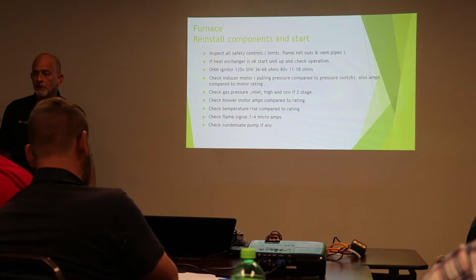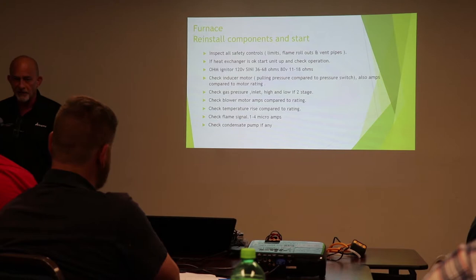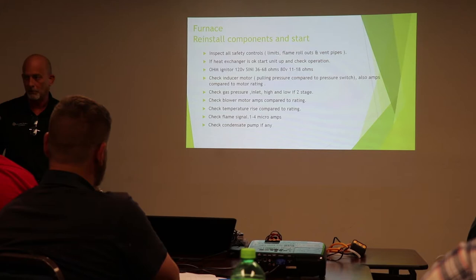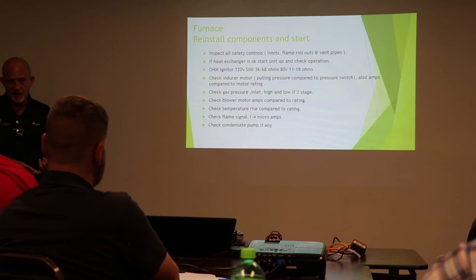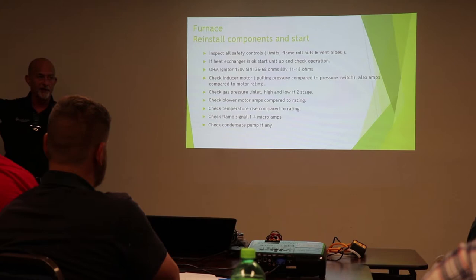Also, you want to check condensate pump, if you have a condensate pump, even for an air conditioner, if it's an 80% furnace, make sure that that is working. Make sure the drain is clear. Remember, we're checking the entire system the entire time. How long does it take to check a condensate pump? If you've got a laundry sink right by your furnace, grab a cup of water, pour it in there. It's usually going to dump in the laundry sink if they have no floor drain, so okay, it's working.